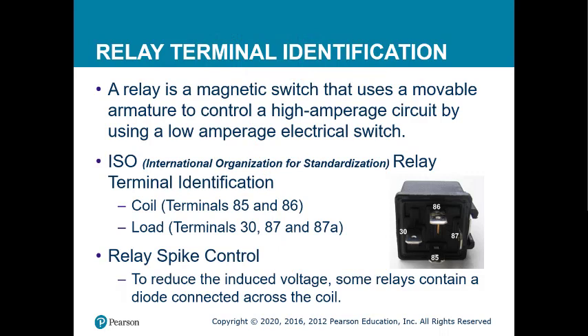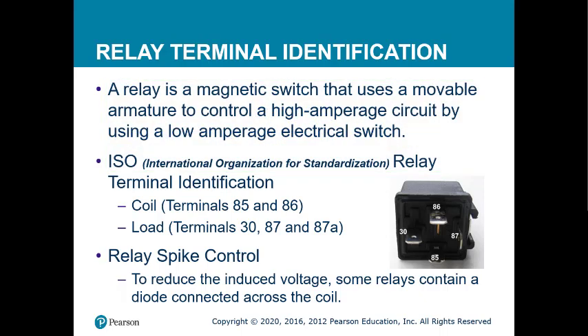Now, the thing we have to understand about relays is because there's a magnetic coil, anytime we energize a coil, it creates a magnetic field. When you turn that coil off, that magnetic field will dissipate. And when that magnetic field dissipates, it releases a blast of voltage. It's called a voltage spike, otherwise known as counter electromotive force, or CEMF. We have to have a way to control that. So we use things like diodes and resistors. So that's referred to as relay spike control.